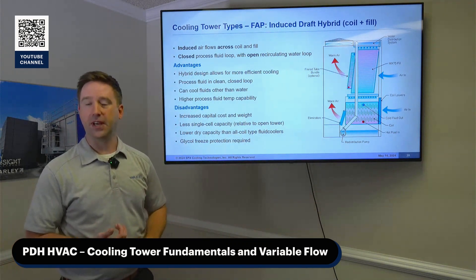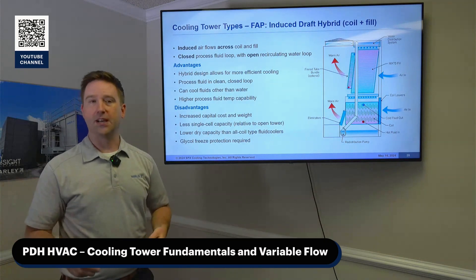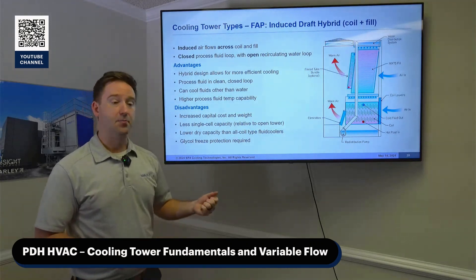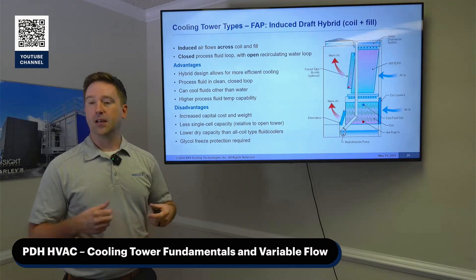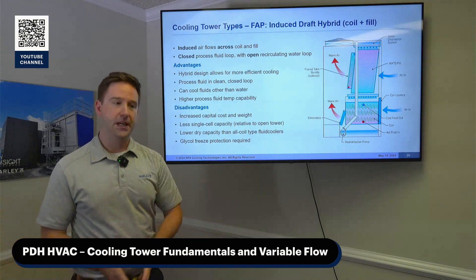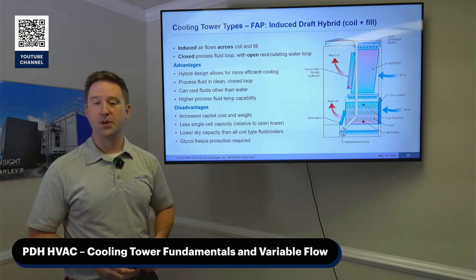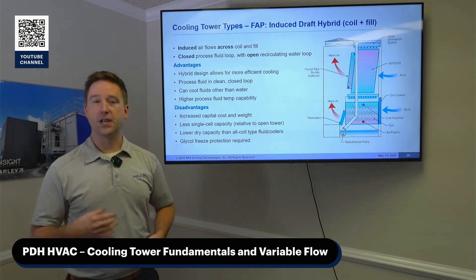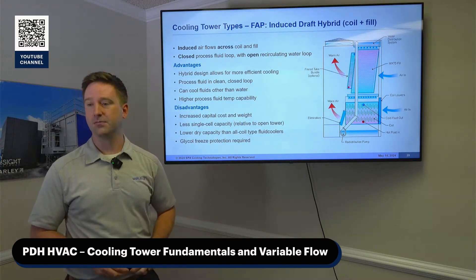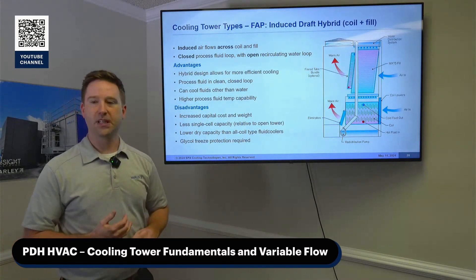There are several coil types. Galvanized is typically the cheapest, but the inside of that coil is raw steel — you don't want to drain it when not in operation because air contact will cause corrosion and pinhole leaks. Stainless steel can be drained and is very durable, but less efficient for heat transfer. Copper coils offer excellent heat transfer efficiency, can be drained in the wintertime, and — looking at lifecycle cost — a large copper coil can be recycled 15 to 30 years down the road, likely for more than the original cost of the fluid cooler.